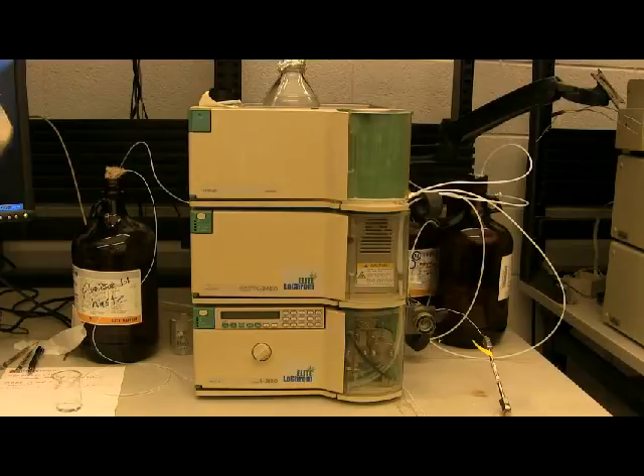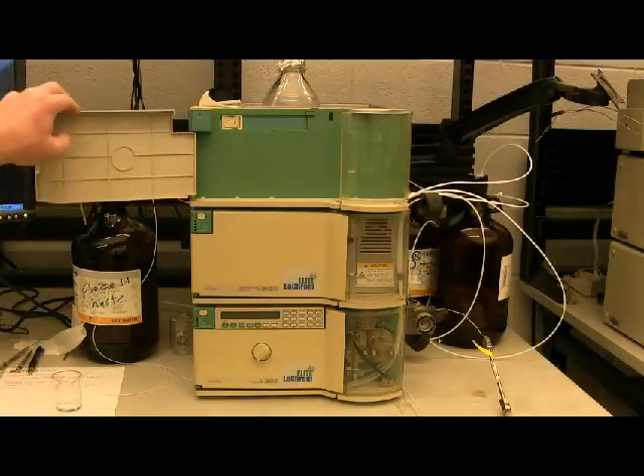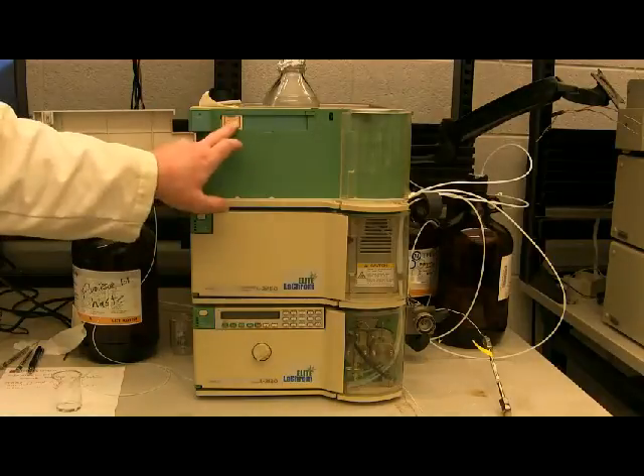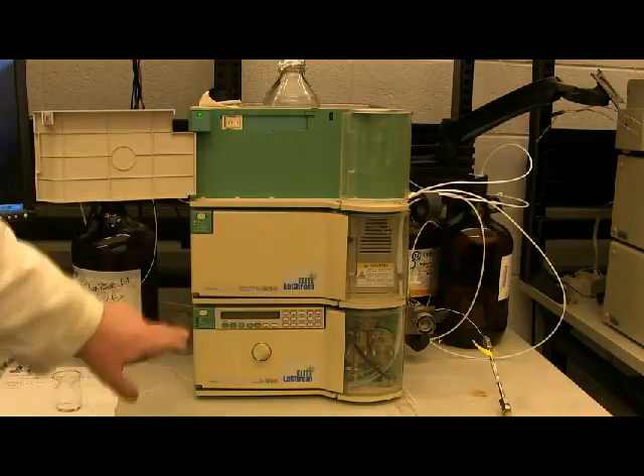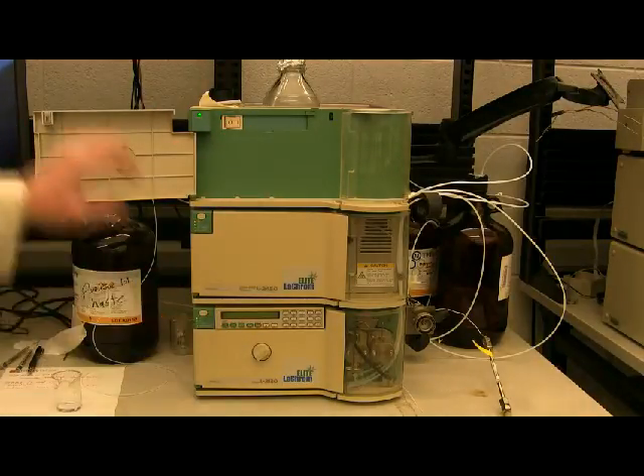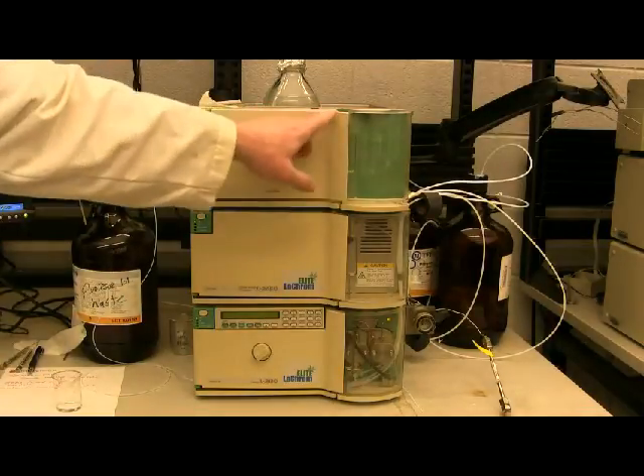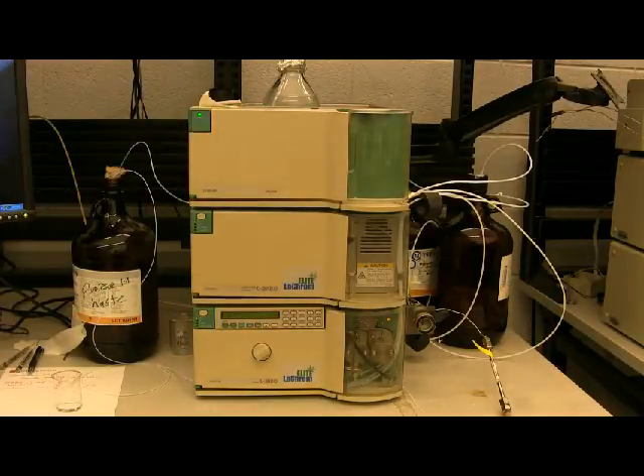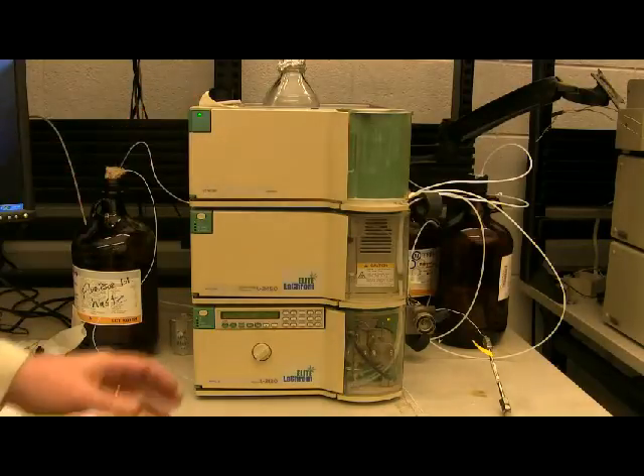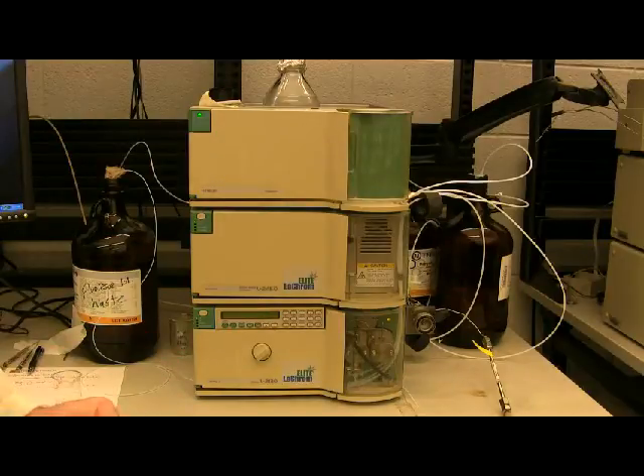So to get started first, let's turn the instrument on. You go from top to bottom, with the pump being turned on last. The next thing we want to do, since it is a fluidic system, we want to make sure there's no air in the lines. The way we do this is as such.